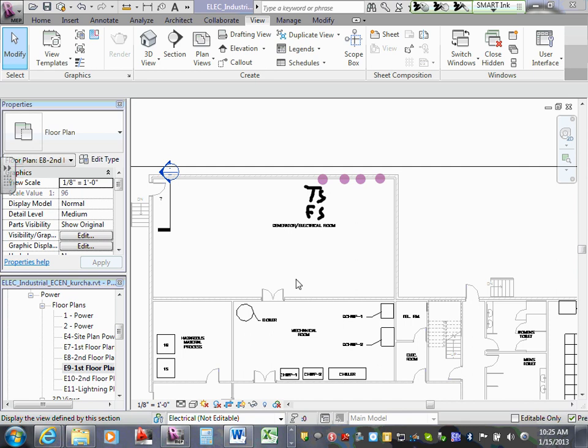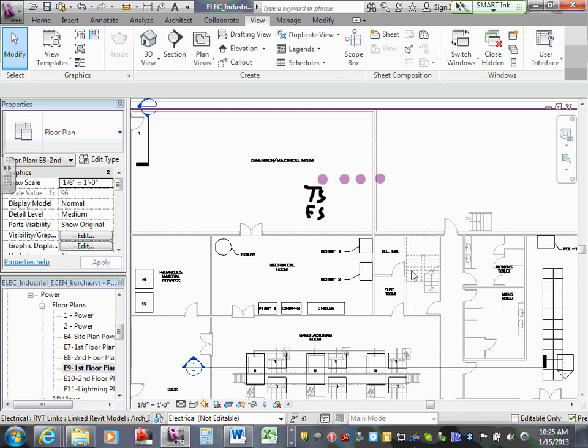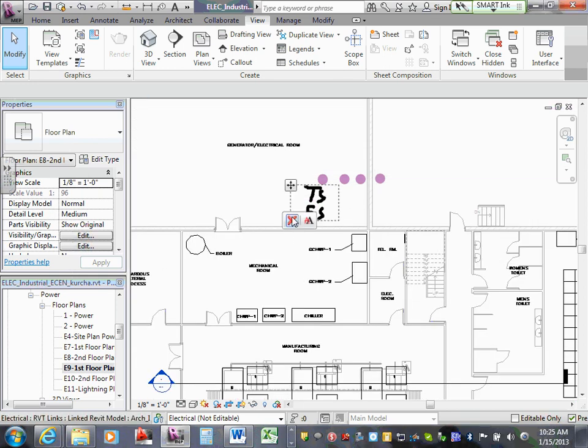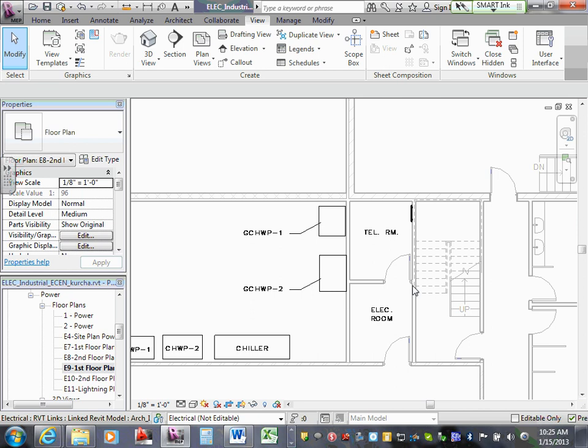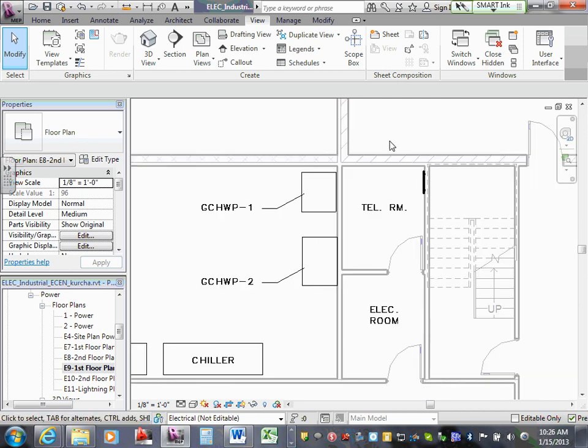They've gone away from it in code, but they brought it back in the NFPA 2010, is that at every panel, power supply that you're putting into the fire alarm system, you must have a smoke detector above it. So in your electrical, if this is where your fire alarm control panel is, you're going to have a smoke detector and a manual pull station next to it. Matt, is it okay to put in a telephone? Yeah. Low voltage? Doesn't have to be in the electrical. No. Right now the low voltage we're gonna put them all here and leave this one for our electrical equipment. You have to have a dedicated breaker for them. So you need a smoke detector right there. Yep, this is right above the panel, and the ceiling above the panel. And the pull station? And a pull station.